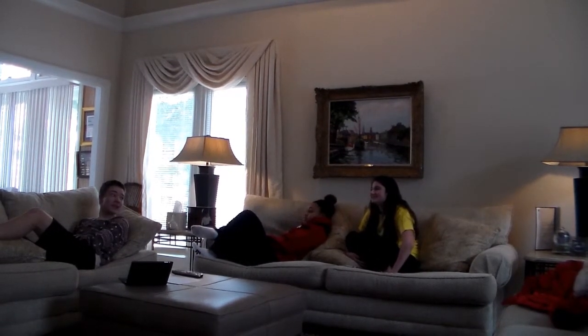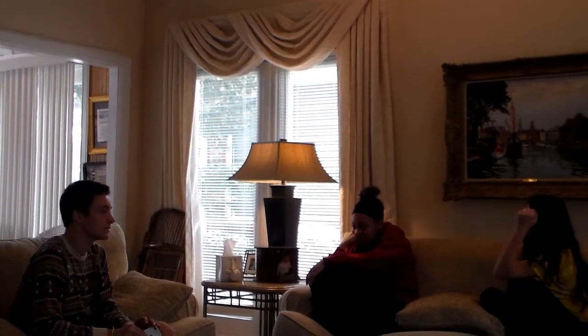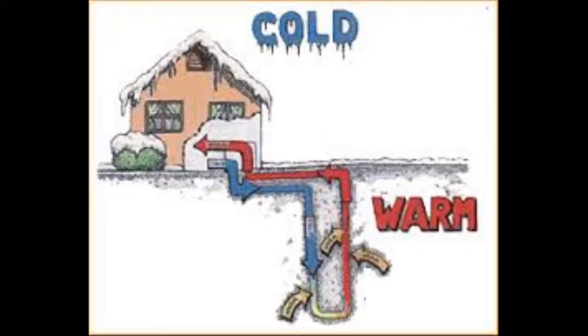What's geothermal heating? What's the difference between a geothermal furnace and a gas furnace? Geothermal uses the Earth's heat. Geothermal heating works when heat is absorbed from the ground and pumped into your house. The water circulating in the earth loop is colder than the surrounding ground. This causes the water to absorb energy in the form of heat from the earth. The water carries this energy to the heat exchanger in the pump. In the heat exchanger, refrigerant absorbs the heat energy from the water.